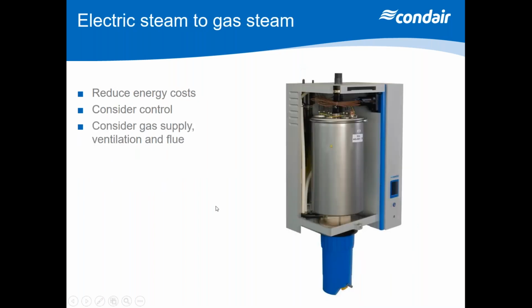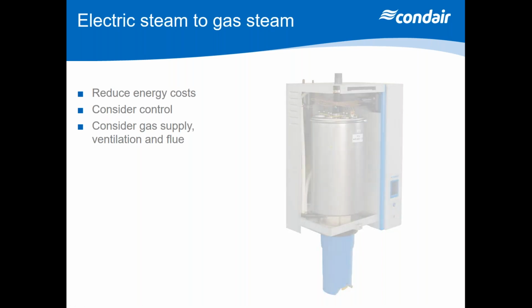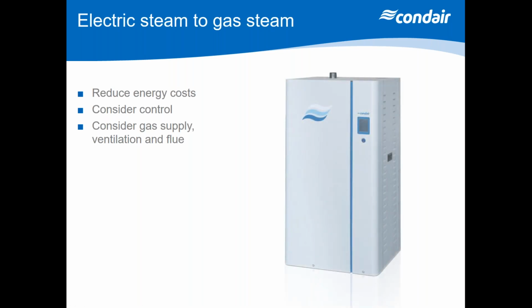If you want to look at big duties using an electric steam unit at the moment, you go to gas. What you've got to consider is if you go to gas, the turn down rate on a gas burner isn't going to be anywhere near as good as what a resistive humidifier will give you in controllability. So if you've got a wide control band, say plus or minus 10%, and a slow air change rate, then gas might be the way to go. You've got to save energy. But what you've got to consider is you're looking at the gas supply, ventilation and flue in addition to the unit. So if that's not in place, then it might not be an option to look at gas.